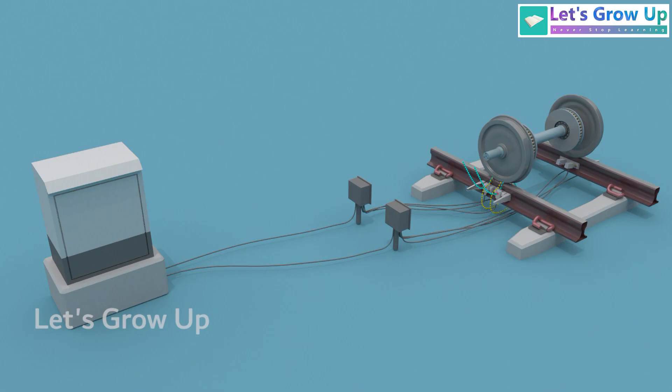Power is needed for two purposes: firstly, to supply voltage ranging from 24 volts DC to 60 volts DC for indoor equipment connected to the evaluator box; and secondly, to provide a constant voltage of 70 volts DC for the external operation of up to five counting heads.